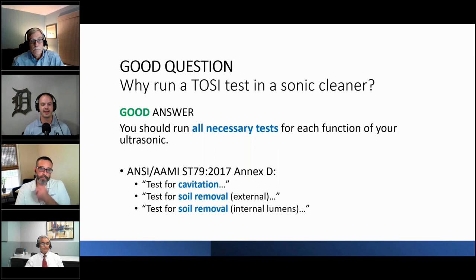If you're familiar with Annex D of ST79, it gets a lot more specific about what tests to run in our ultrasonic cleaners. It states to test for cavitation, like we mentioned. It states to test for soil removal from external surfaces. And it also says to test for soil removal of internal surfaces like lumens or cannulated items, things like that.